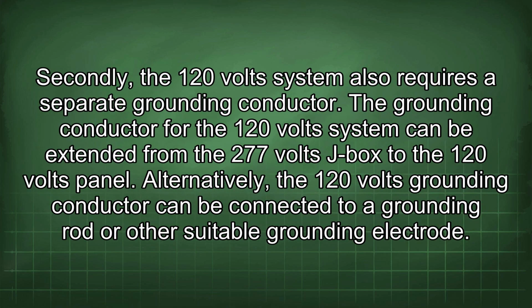Secondly, the 120 volt system also requires a separate grounding conductor. The grounding conductor for the 120 volt system can be extended from the 277 volt J-box to the 120 volt panel. Alternatively, the 120 volt grounding conductor can be connected to a grounding rod or other suitable grounding electrode.